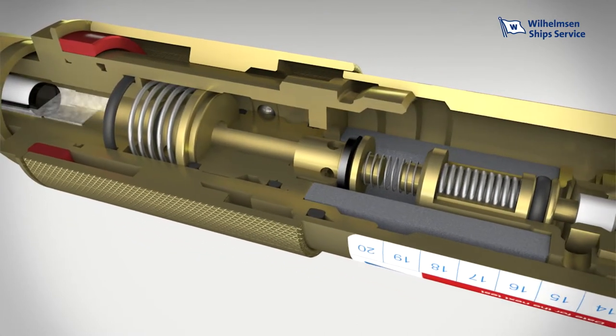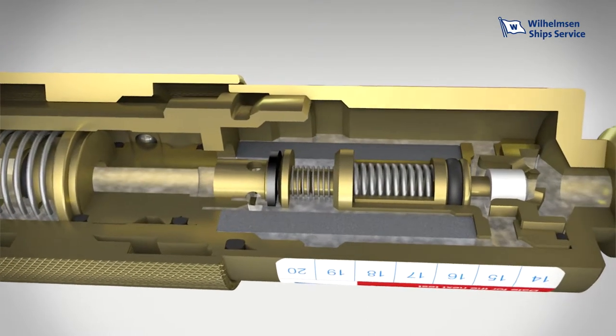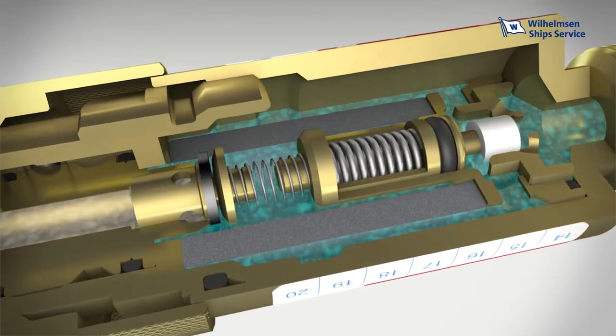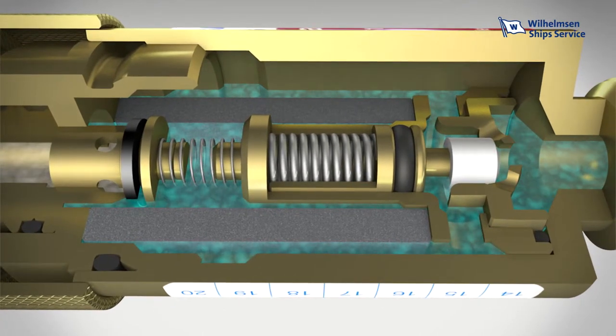Let's have a look at the principle behind the Flashback Arrester in more detail. If a hazardous situation arises and unwanted gases flow through the pipeline, the spring-loaded non-return valve will come into action. It stops the return flow instantaneously, thereby preventing the formation of an explosive gas mixture.